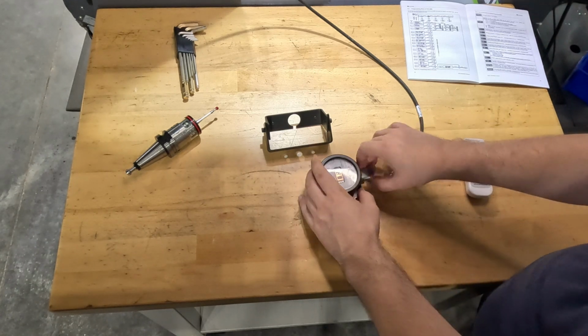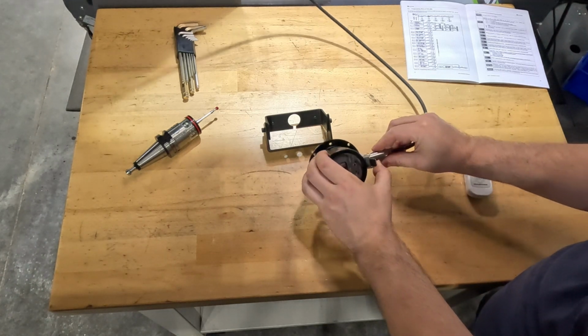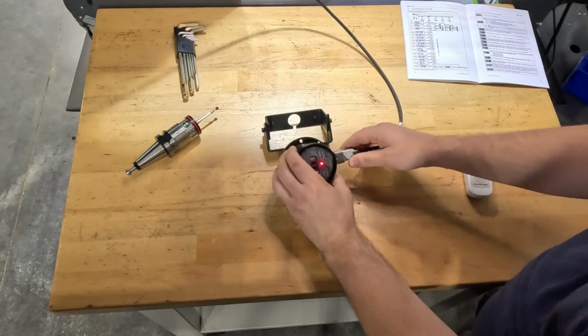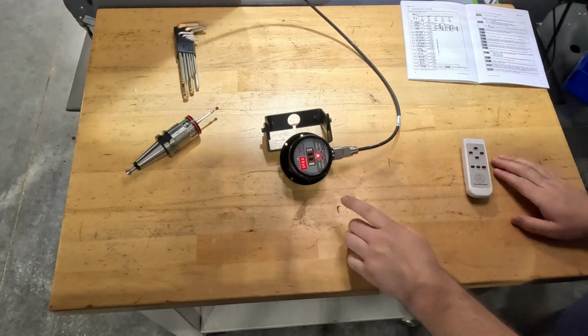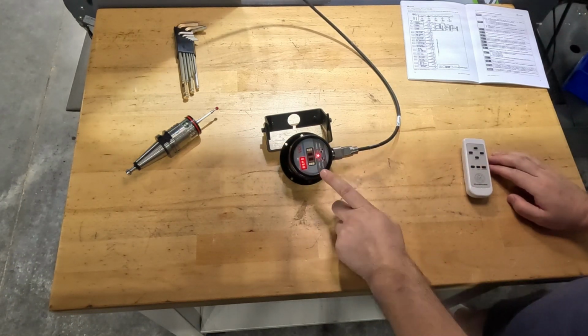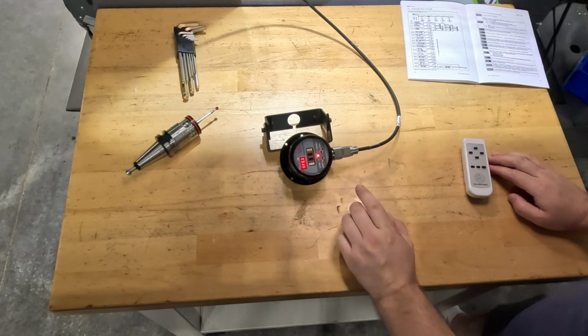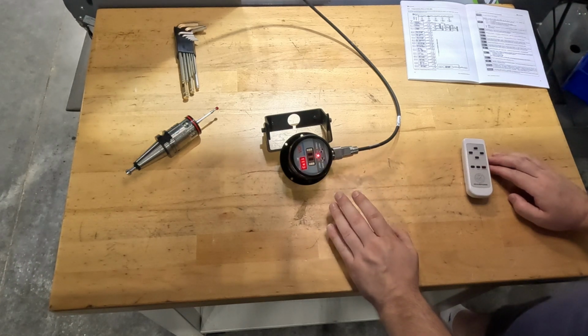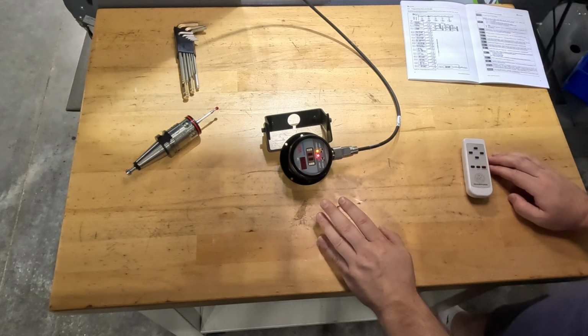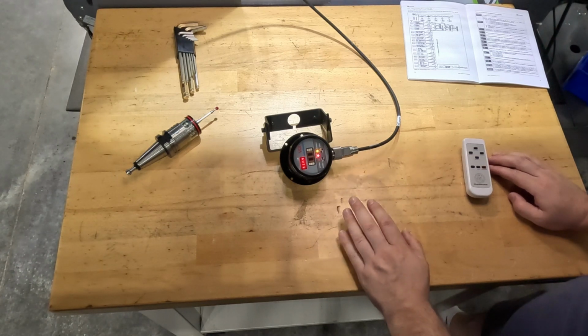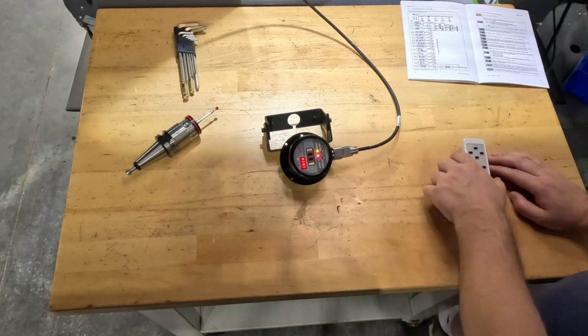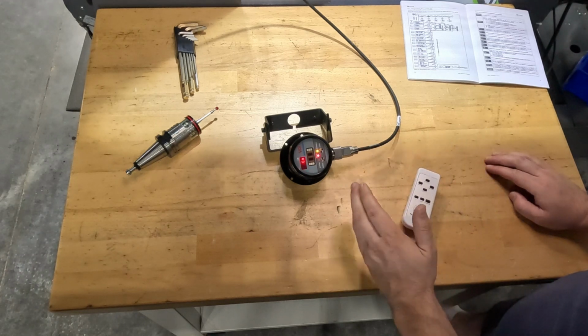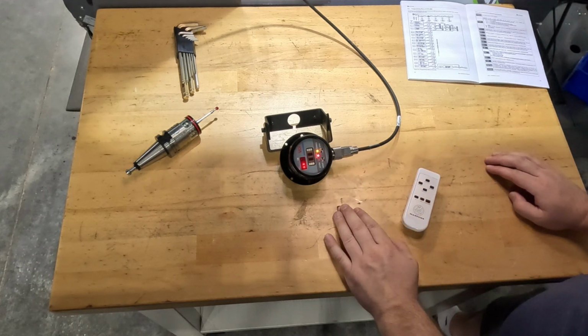So first thing I'm going to do is plug in our cable here to our receiver. And our display turns on here. This is going to start saying calibrating, and it'll do that for about 35 seconds. Anytime the receiver is saying calibrating, you're not able to do any probing with the probe or ETS or to set any settings. It just won't work until the internal calibration is done.